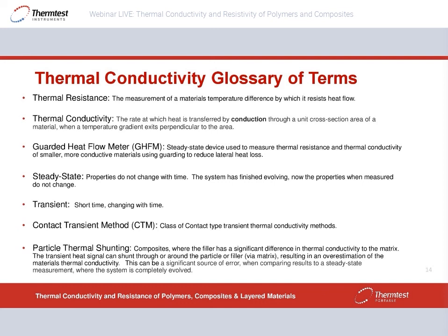I want to test thermal pad with 0.3 to 10 millimeters. Of course, this device is well designed for thermal interface material. ASTM E1530 is very typically used.